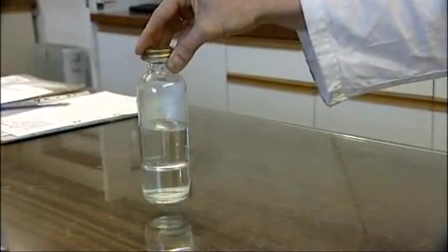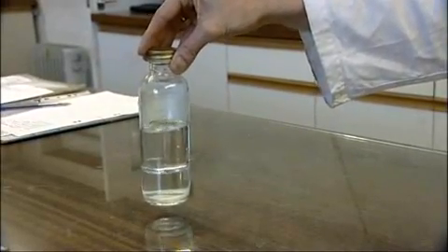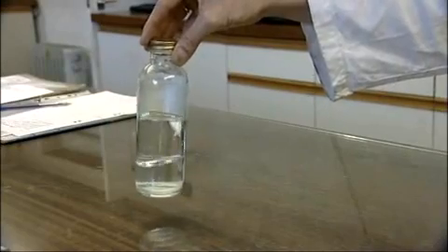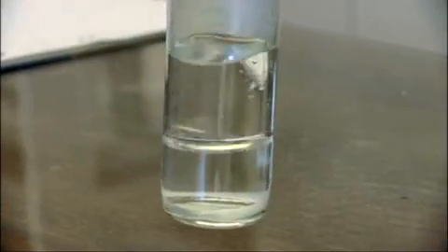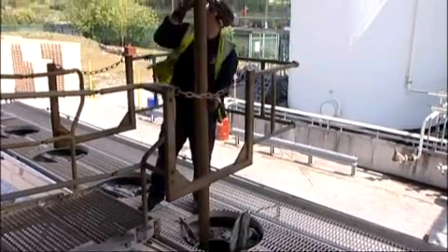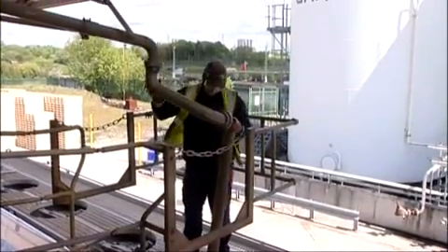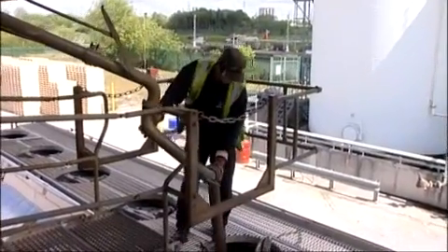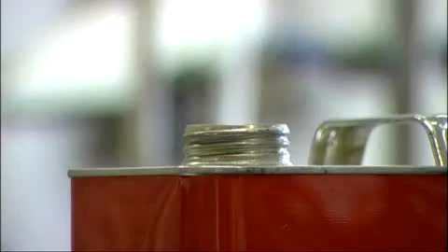Storage tanks can contain a small amount of second phase, for example water, and the relaxation time should be considerably longer than for the pure solvent. Care must be taken when the receiving tank, compartment or container has not been cleaned out and contains flammable vapor, particularly when the next liquid has low conductivity.